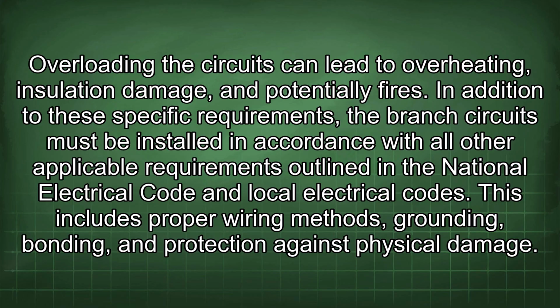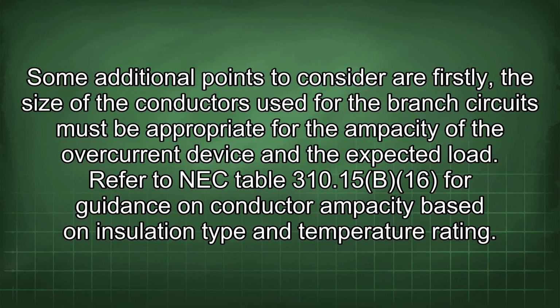In addition to these specific requirements, the branch circuits must be installed in accordance with all other applicable requirements outlined in the National Electrical Code and local electrical codes. This includes proper wiring methods, grounding, bonding, and protection against physical damage. Some additional points to consider are: firstly, the size of the conductors used for the branch circuits must be appropriate for the ampacity of the overcurrent device and the expected load.